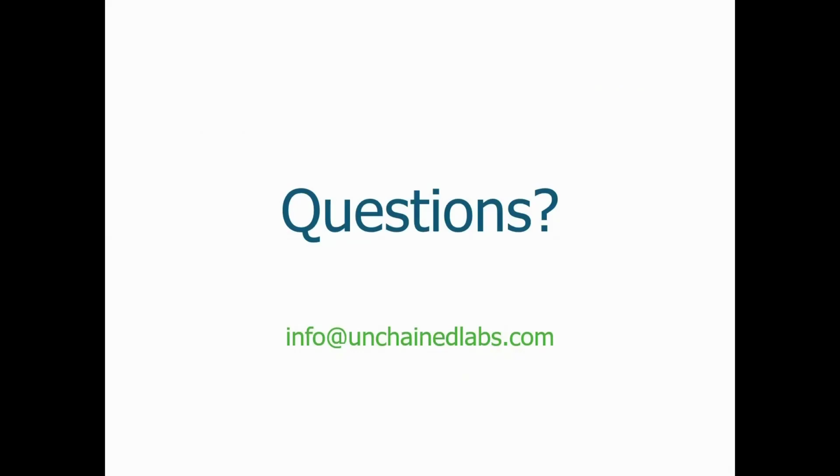All right. Our next question, how flexible are the new isothermal apps in UNCLE? Thanks for that one. As I mentioned, there are 5 isothermal apps, and I'm grouping the out-of-the-box apps together with the regular isothermal. So we have one isothermal that gives you full flexibility of using either of the 2 lasers for SLS and fluorescence, and also the DLS system. Then we have an isothermal application that is using only the blue laser. That would be something for dyes. We call that isothermal stability with SYPRO. And then we also have an isothermal capsid stability that would be used for the viral vector applications, where we would use a dye like SYBR Gold.